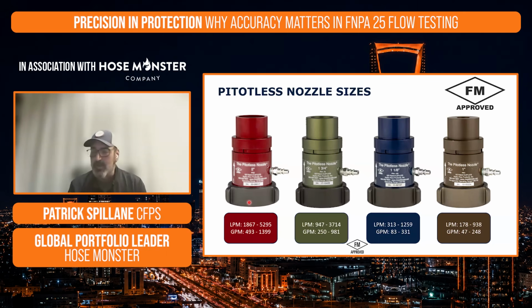We can also get these adapted to the proper connection for your region. So whether you're using a British instantaneous coupling or a national hose thread or a national standard thread, we can get you the proper adapter to connect to any of your water flow devices. But as you can see, each different nozzle size has a different range of accurate measurements. So our 2-inch pitotless nozzle is going to be great for large flows when you're hooking up to a hydrant and you want to maximize your flow.